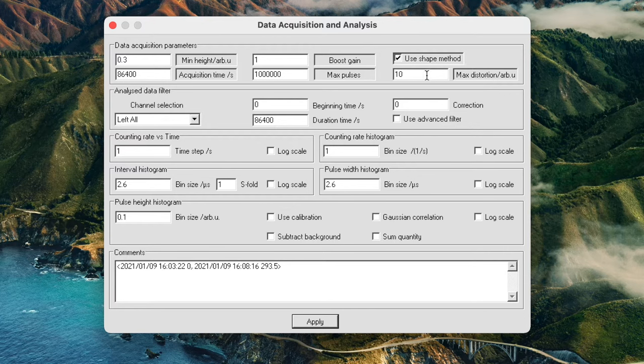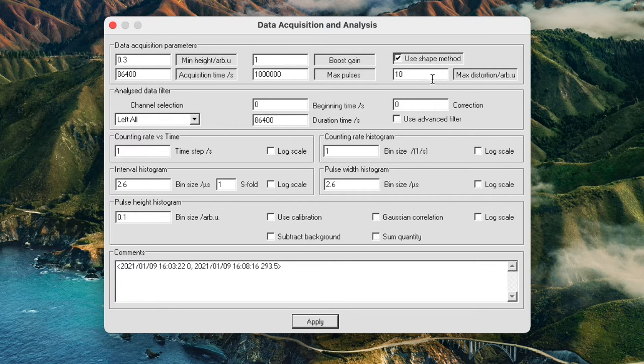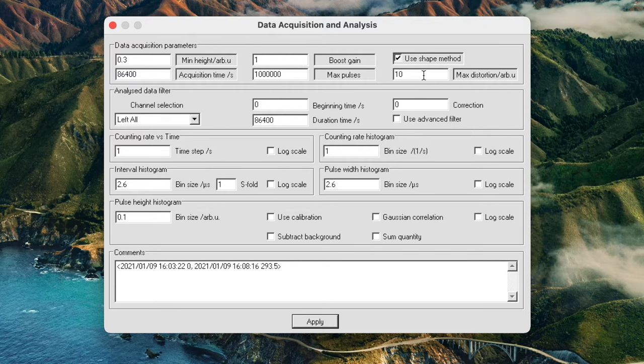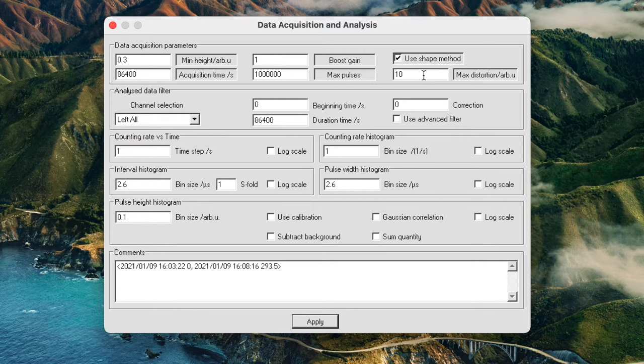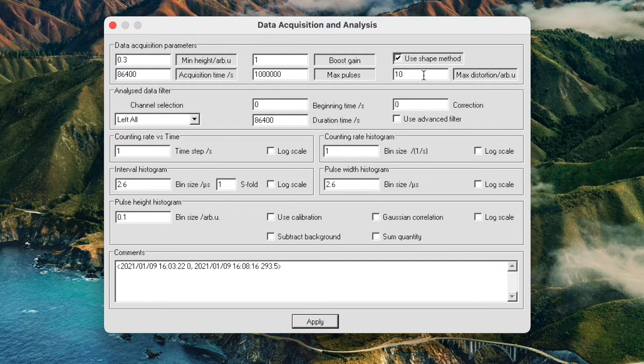The figure under the tick box for the use shape method is the tolerance and you can think of that as a percentage. In this case we're allowing a 10% tolerance on the pulse shape and anything which is outside of that tolerance will simply be discarded. This means that you may sacrifice some of your count rate for a higher resolution. The only time you would leave this unticked is if you are doing an experiment where you are purely interested in number of counts, not so interested in the resolution of the spectrum.